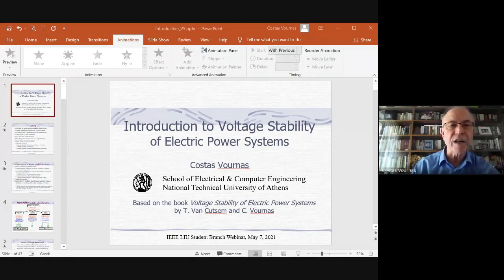Assuming all generators are in synchronism, and assuming we have a global balance between active power generation and active power load—meaning in the whole system we have enough power from generators to feed the loads—in voltage stability we are interested in the ability of the combined transmission and generation system to deliver the power requested by loads. So we have the power at the generation; the problem is whether we can transmit this power to the loads. Voltage stability is load driven, whereas rotor angle stability is generator driven.